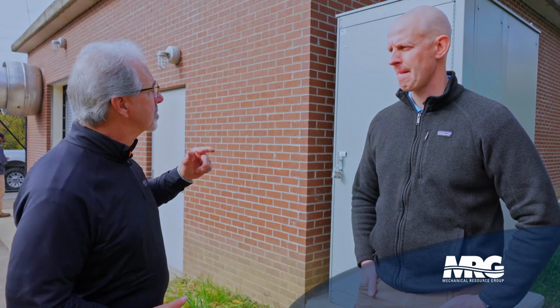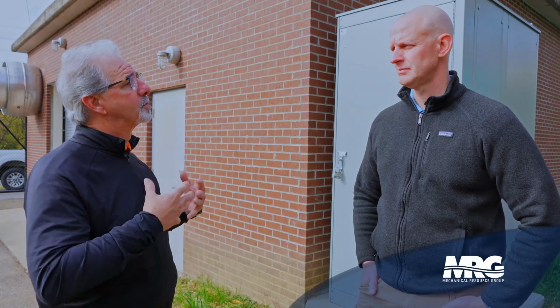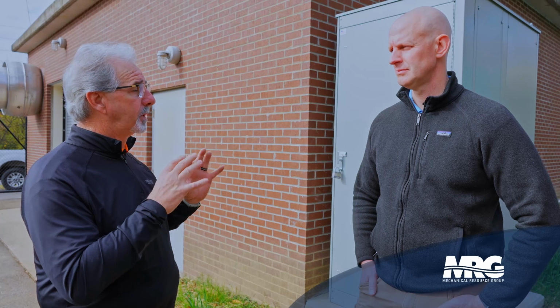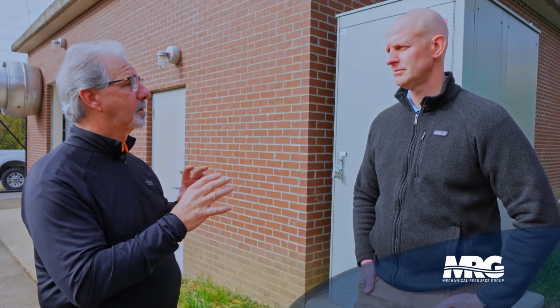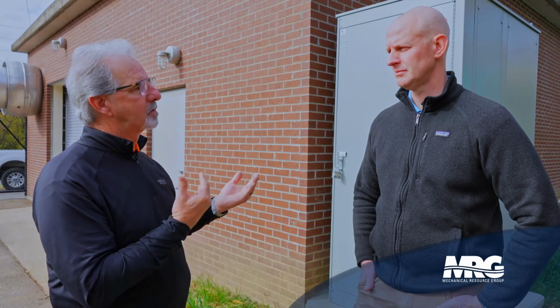We could potentially have a lot of power coming out. We've got an automatic transfer switch here. Kind of walk me through what we're doing there. Well, it's a voltage source. It looks to make sure, for one, that the generator is not running, but it's also monitoring utility power. As soon as it senses either a brownout or a complete blackout, we go into a 100 millisecond transfer. Before that, the generator will come up, speed up to speed, and be at a rotational value where it can negotiate waveform. Once it does that, it makes that transition, and now we're on generator power, and we are no longer looking at utility power. Gotcha.